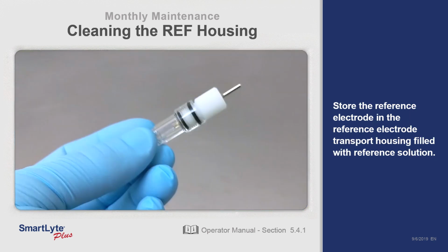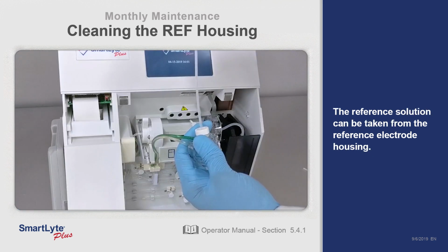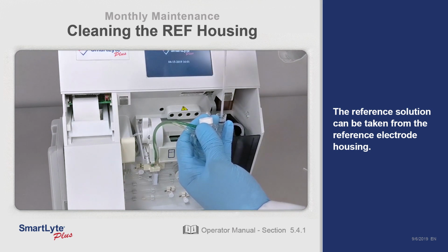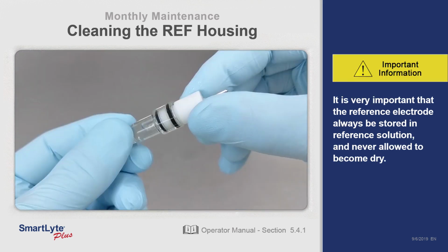Store the reference electrode in the reference electrode transport housing filled with reference solution. The reference solution can be taken from the reference electrode housing. It is very important that the reference electrode always be stored in reference solution and never allowed to become dry.